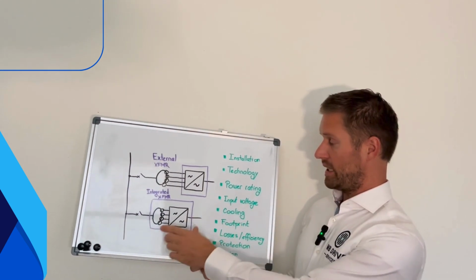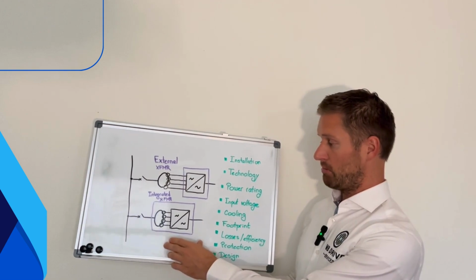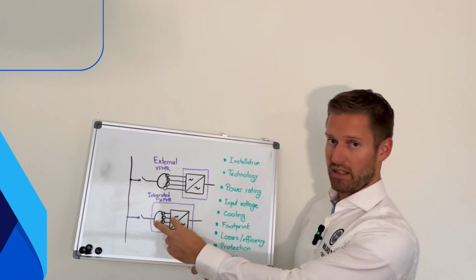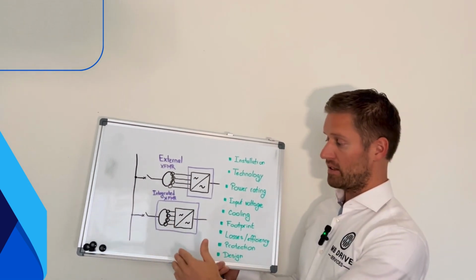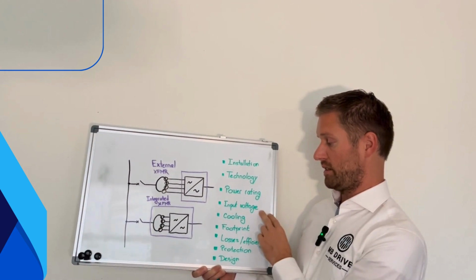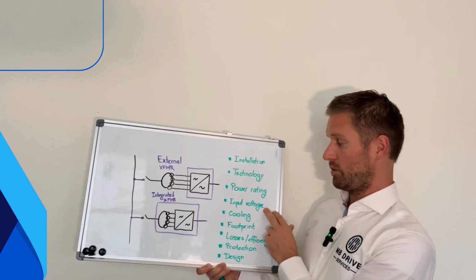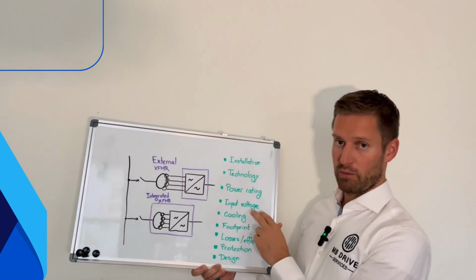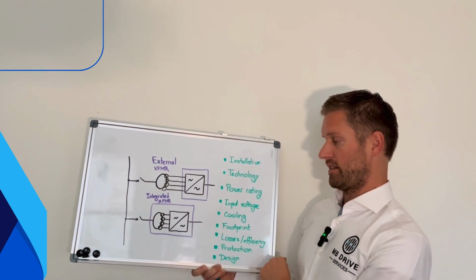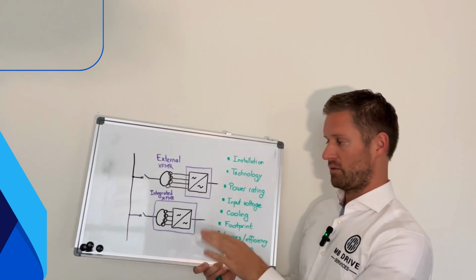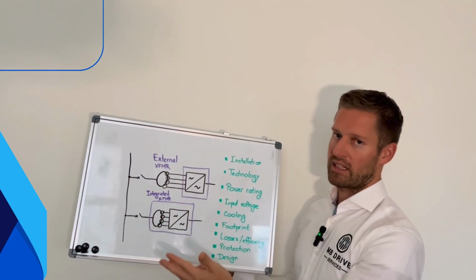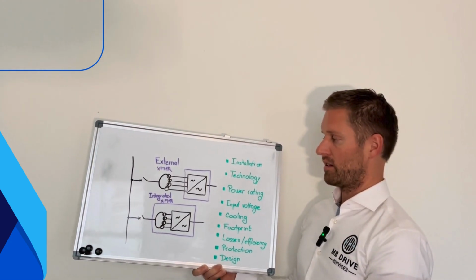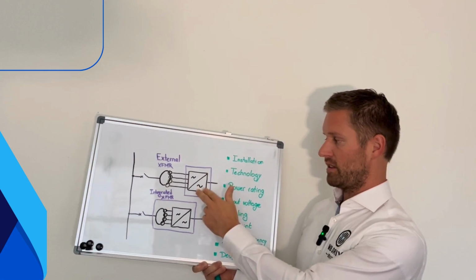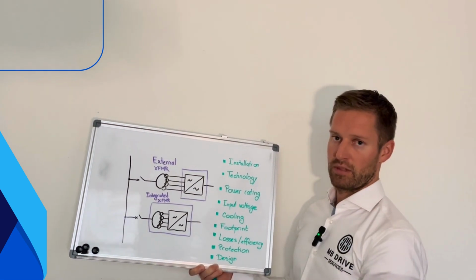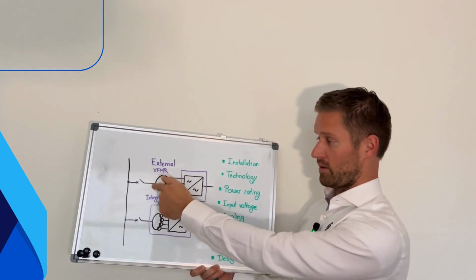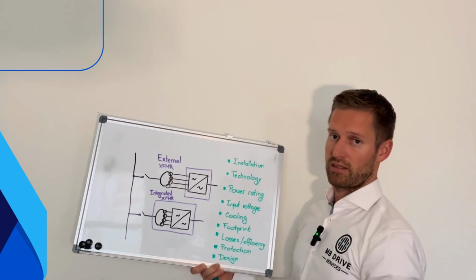Input voltage, similar, the integrated transformer is limited in input voltage. It comes again from the fact that the transformer is inside the enclosure, so we have certain clearances, and we cannot go too high with the input voltage. So typically the input voltage goes up to 11 or maybe 13.8 kilovolt, and very rarely higher. But I would say at 20 kilovolt at maximum it's over. With the external transformer, again, you can have practically any voltage. There are several references of larger drives with 132 kilovolt input transformer, so the converter transformer has the primary side connected to the 132 kilovolt.